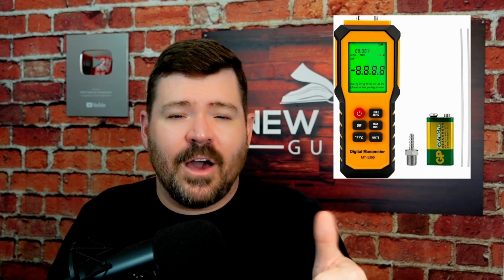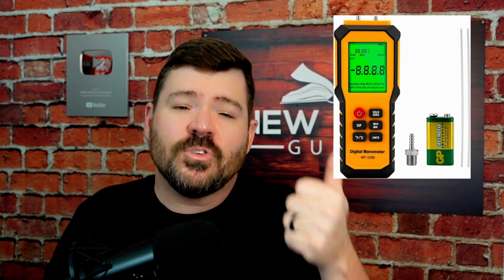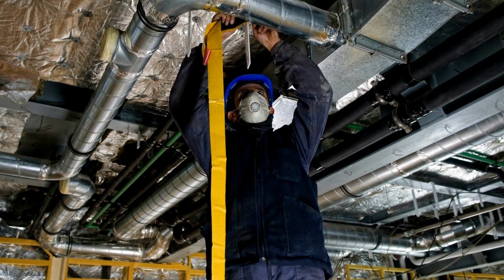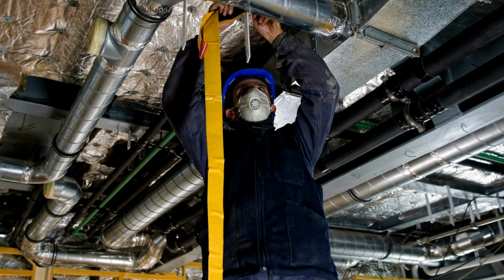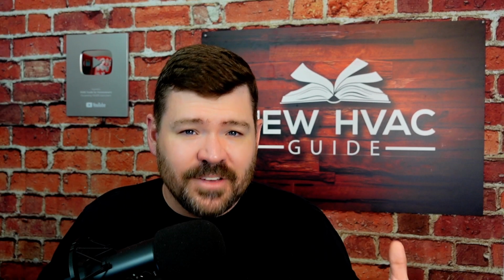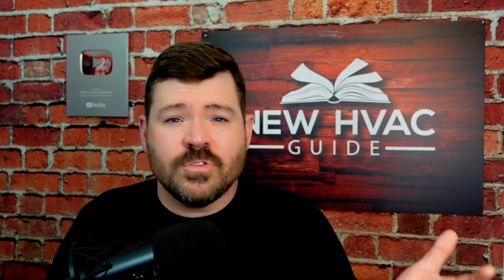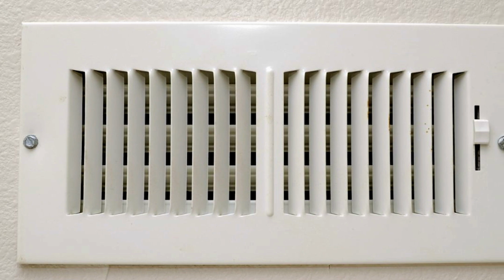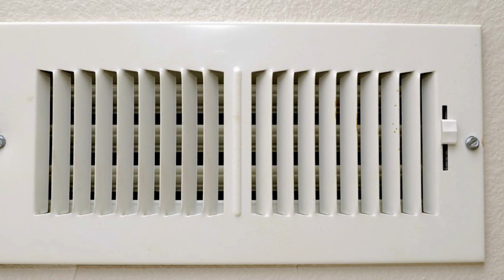That contractor now, whether you stay with the same one that didn't do the job right the first time, or you switch to another one, needs to get their static pressure meter out, manometer, whatever they use. They need to look at the duct sizing and the fact that there is static added to every bend in that system, the length of the system, the sizing of that system, the filter that you use. All of that adds static. Are vents completely open? Are they covered? That again will also add static. Hopefully this helps if you're dealing with any of this.